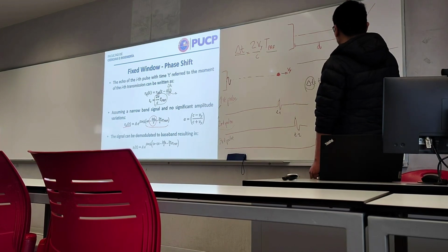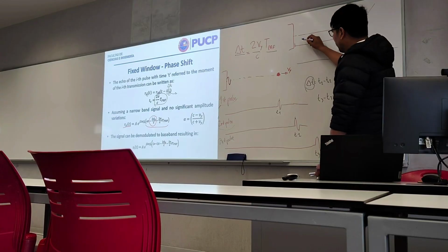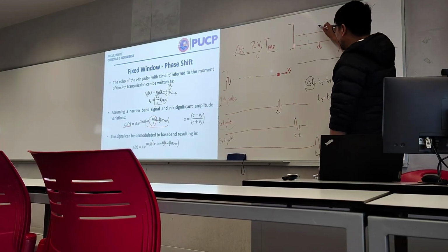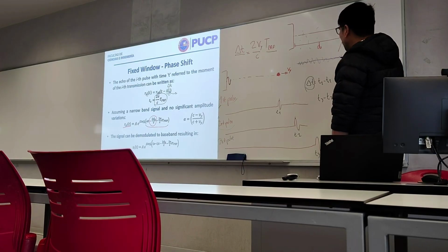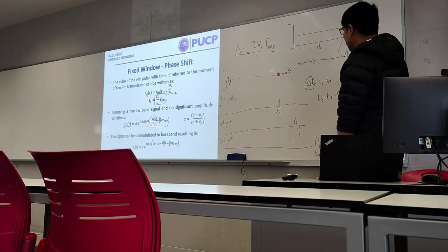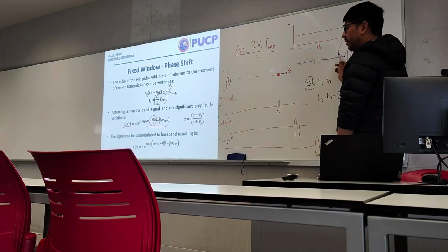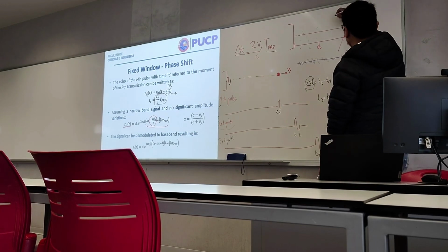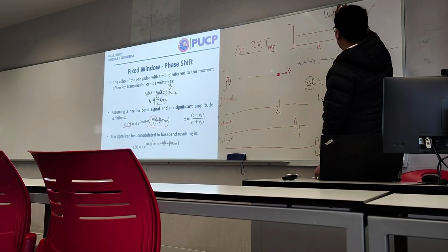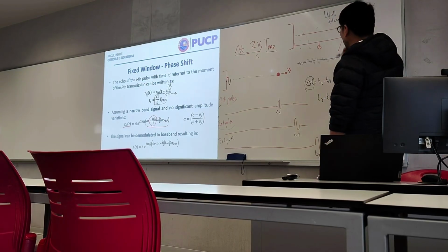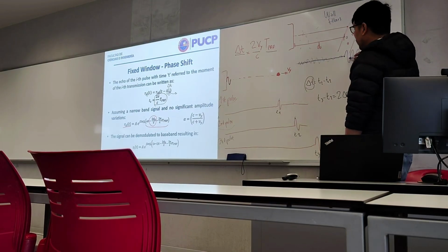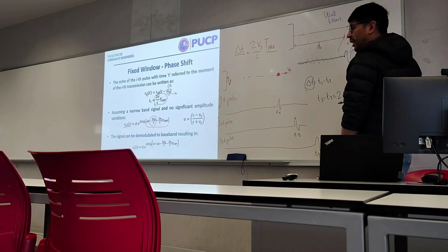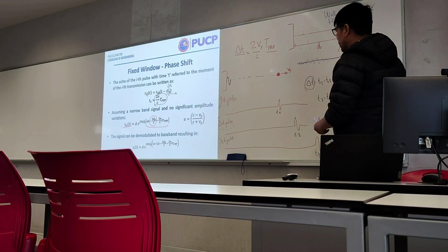Okay. In fact, before that, there can also be scatterers from the tissue, right? But maybe we have some signal too here. It's possible to eliminate them with something called wall filters. I think in a few slides I will mention this too. But at the end, we can just delete this part and keep only the moving parts, the signal that comes from the movement of red blood cells.